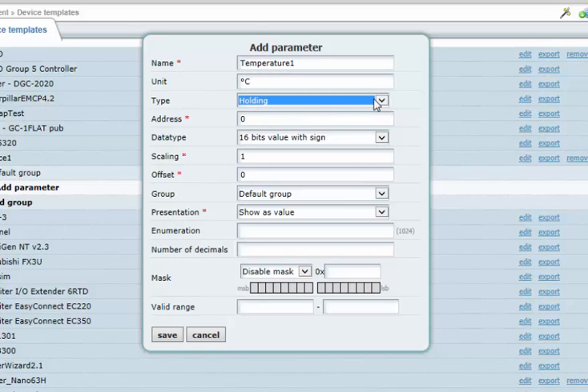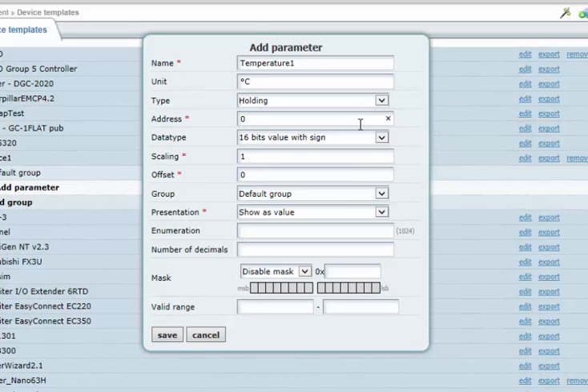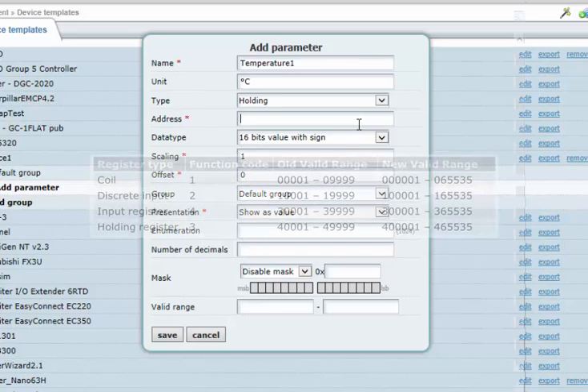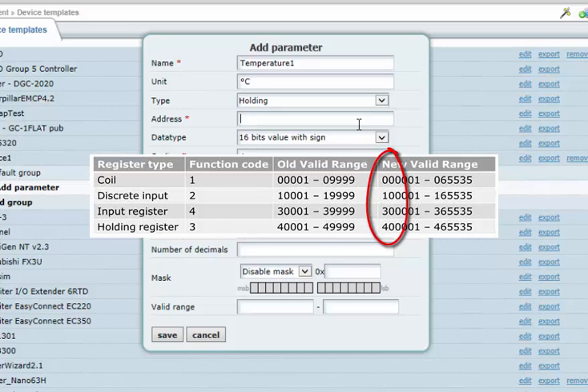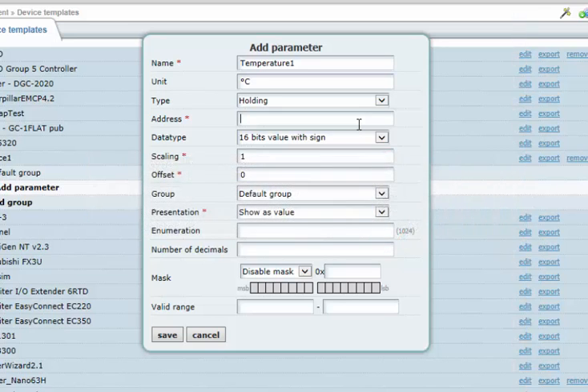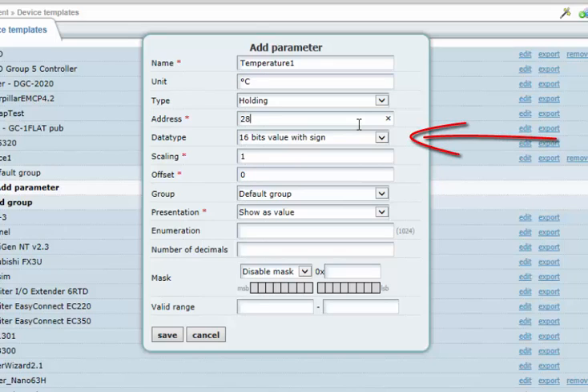The register address required here is the address for the Modbus register in the slave device. This address should be available in the documentation provided with the slave device. Note that it is very common in device documentation for the initial digit in the Modbus address to indicate the type of register. For instance, the address 40028 would indicate a holding register with the address 28.